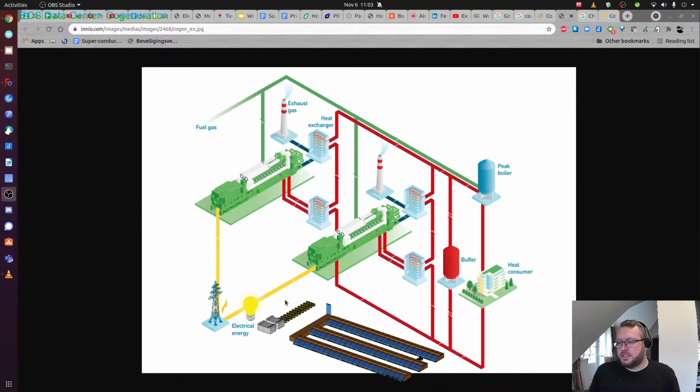Newer technologies in gas gensets make it possible to have gensets that are gas-based and still rev up very quickly. Within 7.5 seconds they can deliver full capacity to the grid. So this can be used and operated not by the data center owner or operator, but rather by the utility, who's familiar with gas power plants anyway.